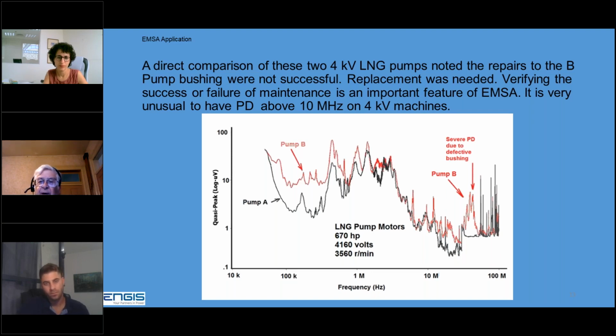So we asked them what the problem was, and they said they had trouble with a 4 kV bushing that they had repaired. Well, the repair was not successful. They needed to pull that B pump and replace that 4 kV bushing.